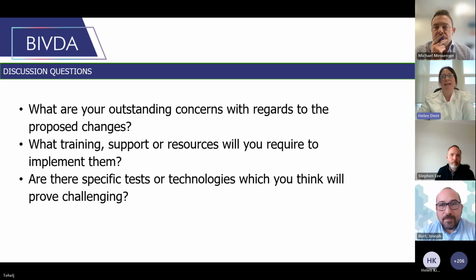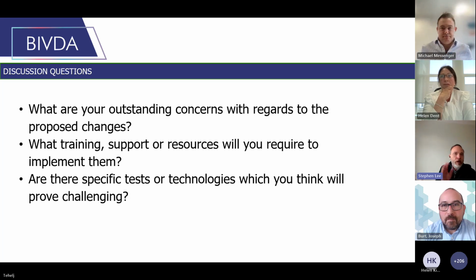Steve, I'll go to you before I ask the next question. Thank you, Helen. Just to add on from a CE marking perspective under IVDR, if it's a genetic test which was not in the scope of IVDD, but is in the scope of IVDR, which I think is where this question is coming from, then it would not have a declaration of conformity to IVDD. Therefore, the transition would be May 2022. So it's already passed. So it would already need to be, unless you're applying the health institution exemption, that's slightly separate. But if it's a CE marked product in the EU, then May 2022 would have been the transition time.